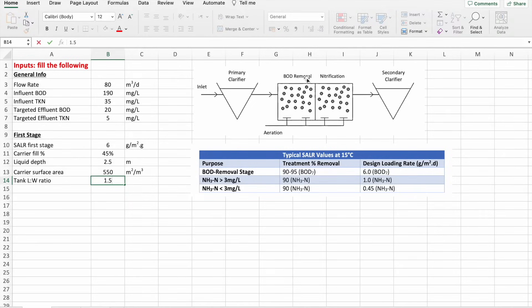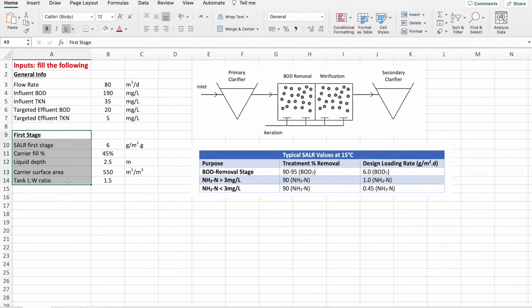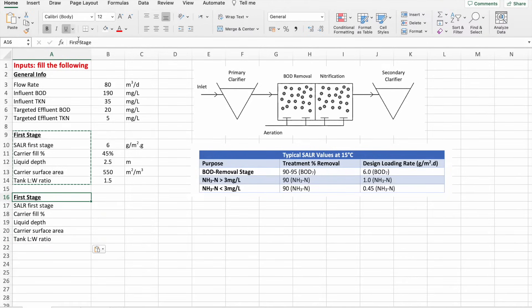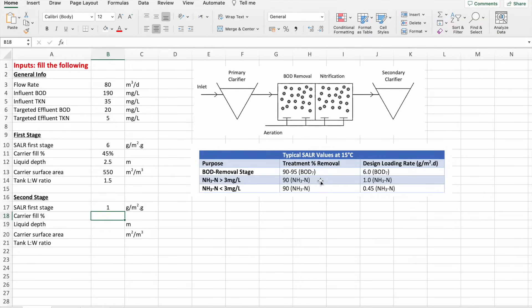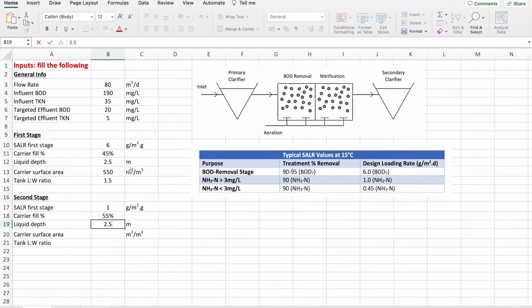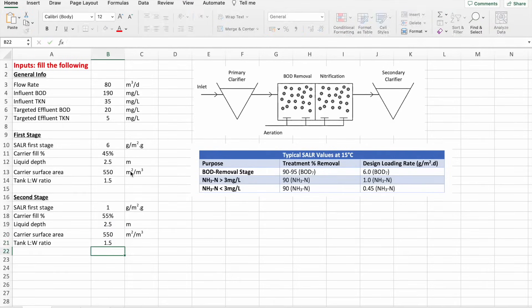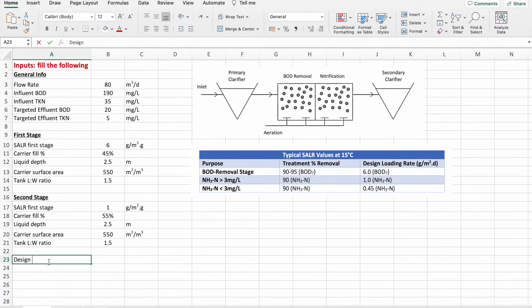Next, we fill in the parameters for the second stage — the nitrification tank. The setup is the same as before. Referring to the SALR table, the value for the second stage is 1. The carrier fill percentage is 55%, the liquid depth is the same as the first stage for construction ease, the carrier surface area is also 550 m²/m³, and the tank length-to-width ratio is the same as before.